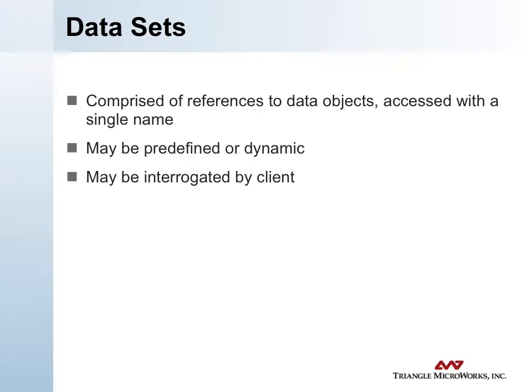Data sets associate a single name with a collection of data object references. A single data object can be in more than one data set at a time. When you access the single name, you get the values of all the members — you can do a get values to read all members or set value to set all members. Data sets can be predefined, meaning static and defined at boot time, or dynamic, where a client can create either a temporary or permanent data set within a server. Data sets can also be interrogated to retrieve their member list without reading the values.